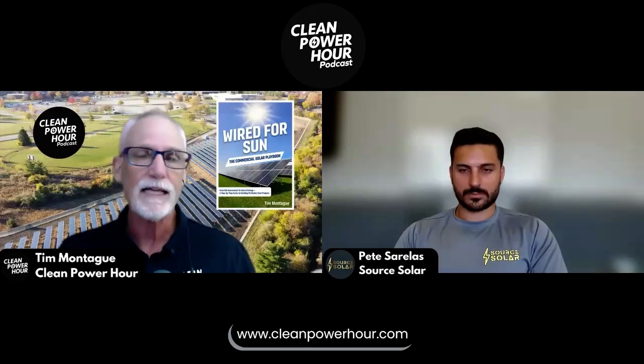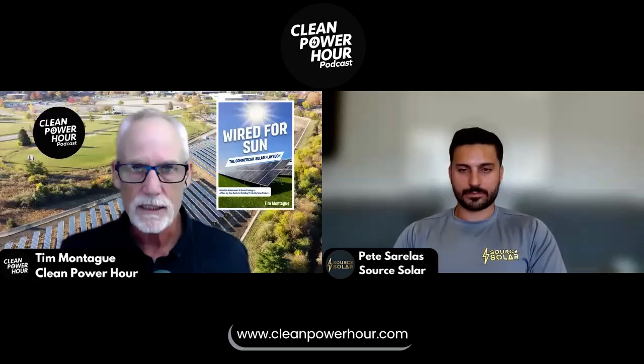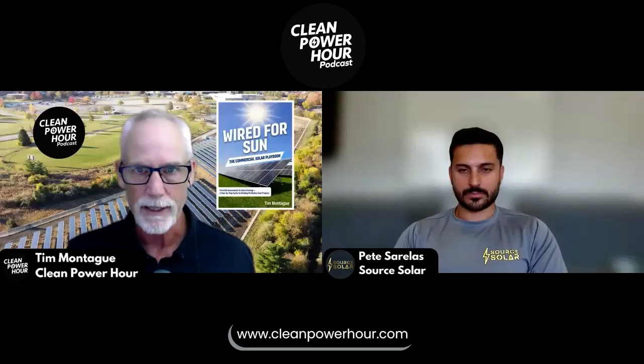How does it work? Let's say they already have solar - how long does it take to get a battery system? If you're installing a 250 to 500 kWh battery, tell us about the process. We're actually usually going a little bigger, typically around that megawatt range for a 4-hour battery, so somewhere around 4,000 to 5,000 kilowatt hours. We're going as big as we can for pretty much anything over that half-megawatt DC system they already have on their roof.